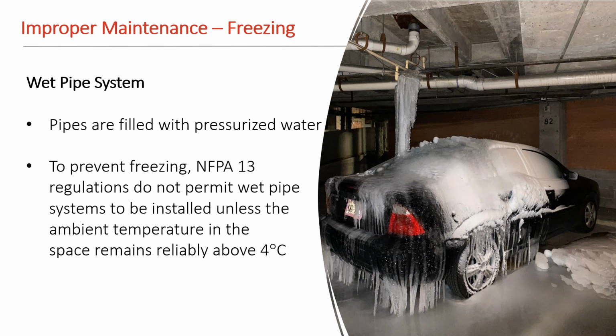And when it comes to the installation to begin with, and we look at NFPA 13, they do not permit the use of wet pipes unless the temperature can be constantly maintained above 4 Celsius. So if you look at a parking garage, most likely it's not going to be guaranteed that it can be maintained above 4 Celsius. However, in some cases, they try to push it a little bit, and well, you can see the result in this case.